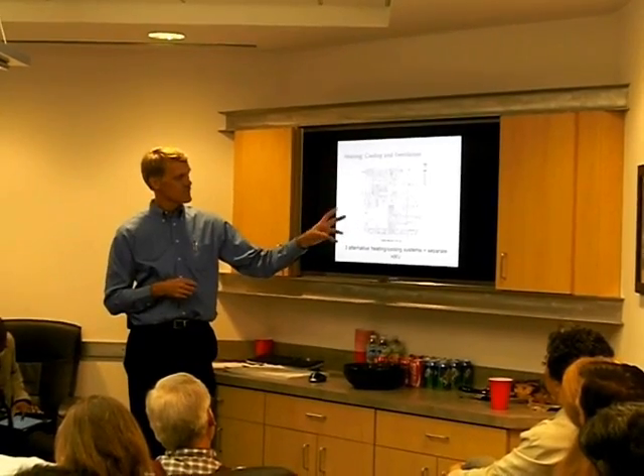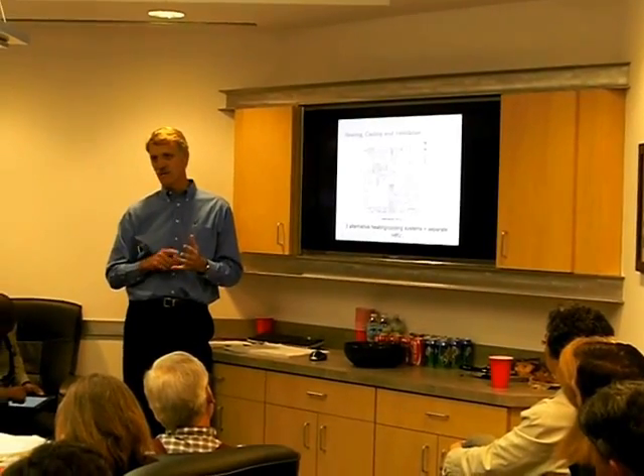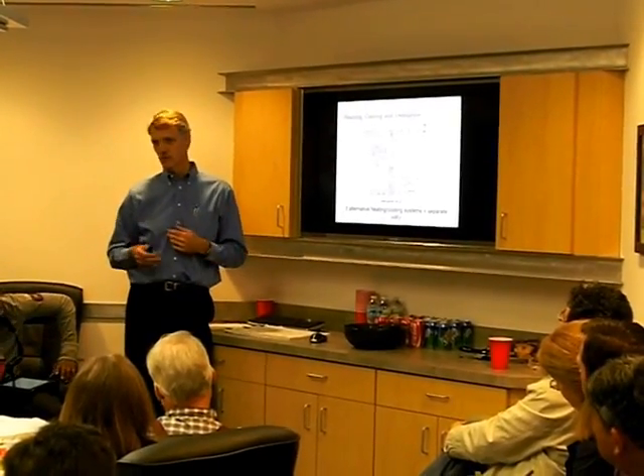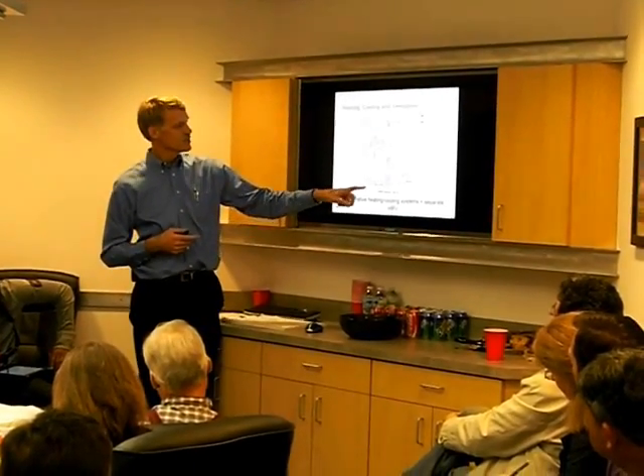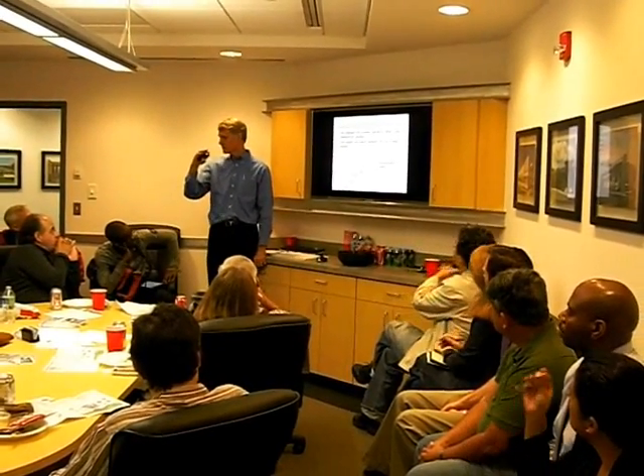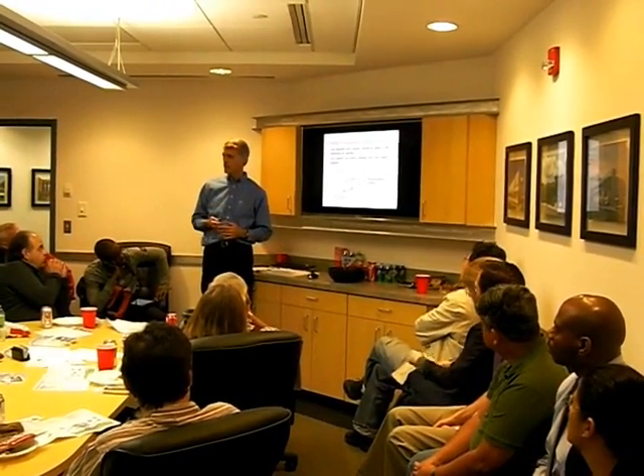You can start to see the intensity of the ductwork runouts that run through. Every room has its own dedicated supply and return, so we're not utilizing undercuts of doors or transfer grilles between rooms — there are actually dedicated supply and return. The duct system can be switched between floor registers and ceiling registers, so at different times of the year it'll switch over and push the air into the ceiling or along the ceiling.